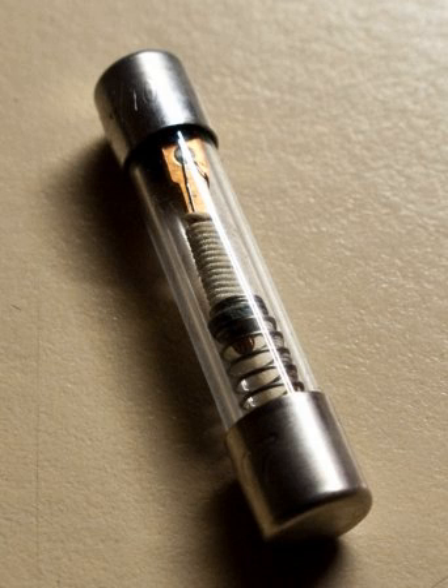Topic: Fuse standards. Topic: IEC 60269 fuses. The International Electrotechnical Commission publishes standard 60269 for low-voltage power fuses. The standard is in four volumes, which describe general requirements: fuses for industrial and commercial applications, fuses for residential applications, and fuses to protect semiconductor devices. The IEC standard unifies several national standards, thereby improving the interchangeability of fuses in international trade. All fuses of different technologies tested to meet IEC standards will have similar time current characteristics, which simplifies design and maintenance.